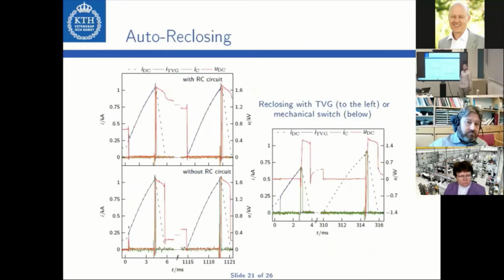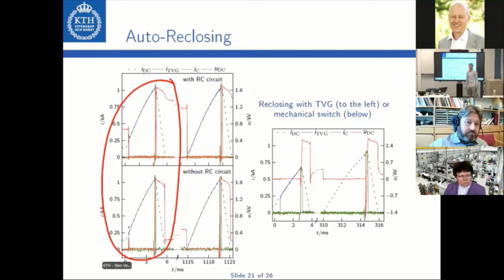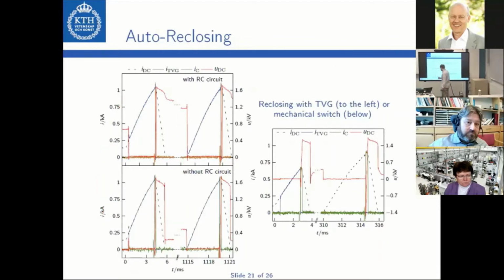We also evaluated the auto reclosing capability. On the left-hand side, you can see the results for auto reclosing operation with the triggered vacuum gap. This first current pulse here corresponds to the first interruption attempt, which is successful, and this process I already described on the previous slide. After approximately 1 second, reclosing is started and the triggered vacuum gap starts to conduct immediately. When the current surpasses the trip level, the injection circuit is again activated to turn off the discharge in the triggered vacuum gap. And we found that this kind of reclosing operation was also reliable.